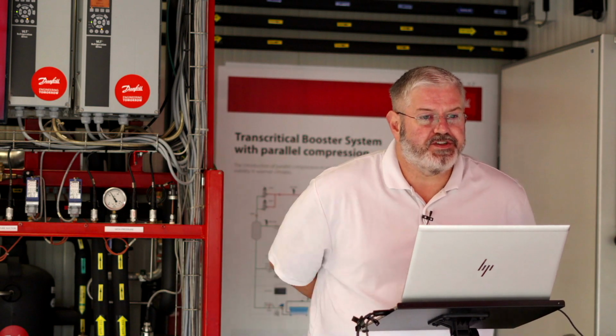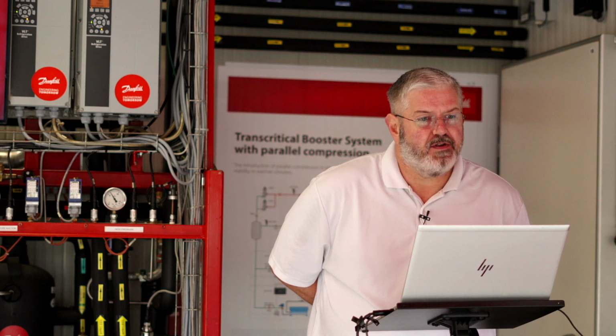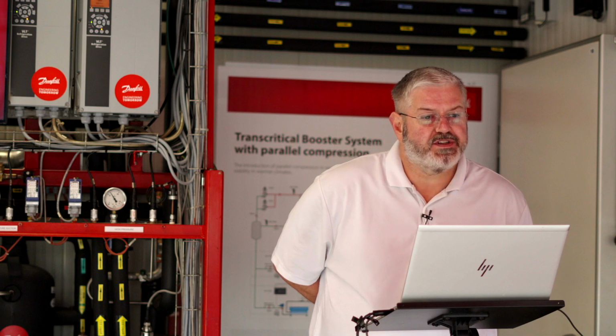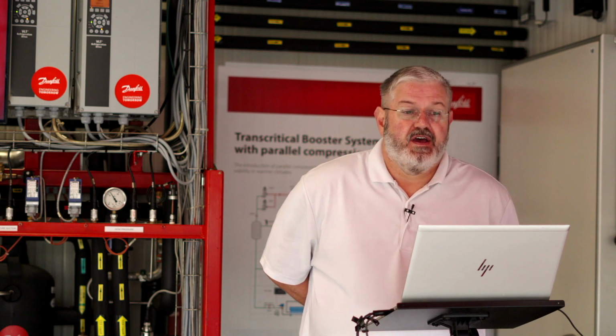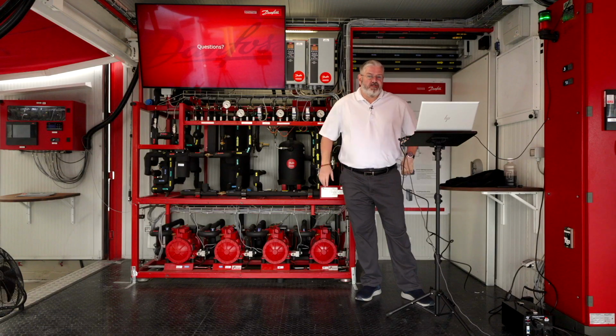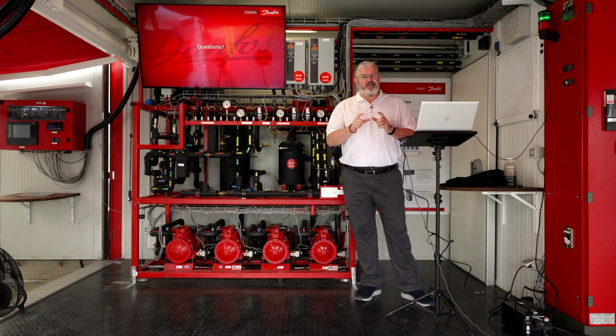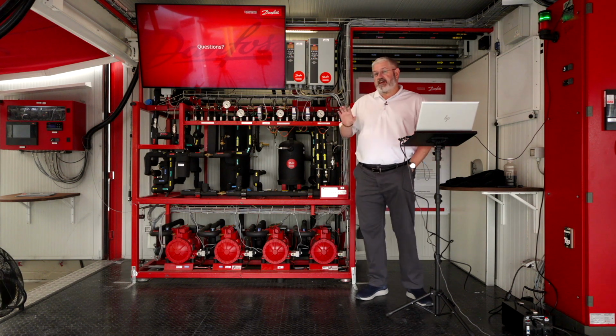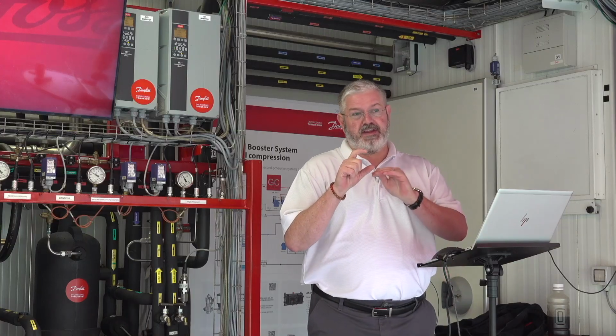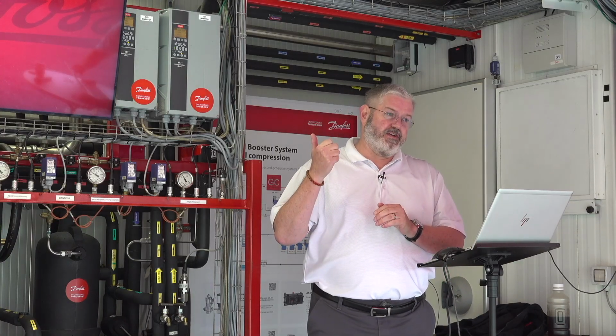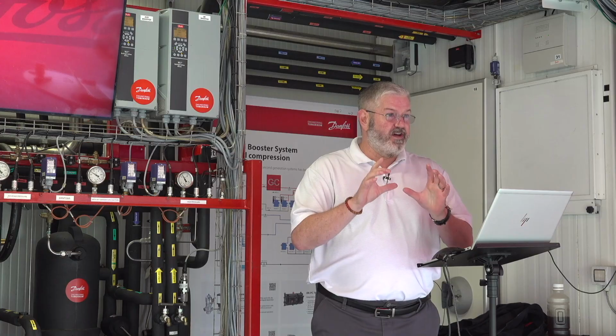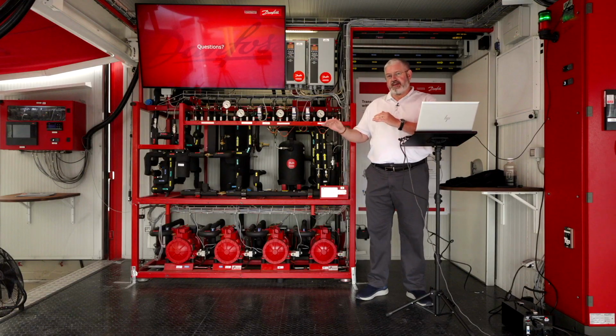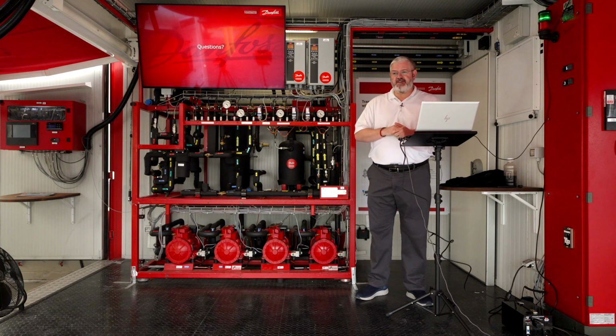So we have a question: is the pressure relief valve stopped from opening if the controller can't get control of the high side of the system? What stops it from opening if the sensors are swapped? So the answer to that question is really no. There's a good and a bad side to a pressure relief valve. The good thing is it doesn't care about the controller. It's a mechanical device, and if it exceeds the pressure it's rated for, it's venting your refrigerant. That's kind of a bad thing because we don't have control of it, but it's good because it doesn't rely on anyone's controller. It's going to protect the system. You want it to do that because you don't want to rupture piping. You don't want to hope it didn't hurt other components.